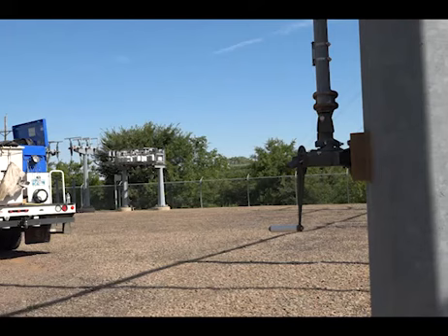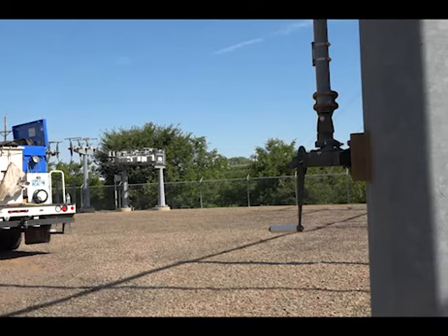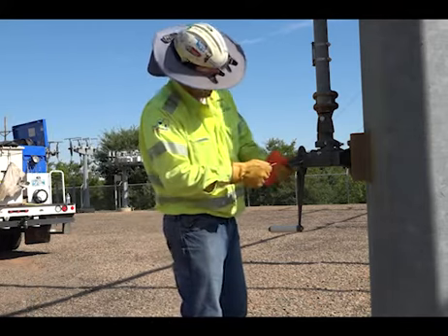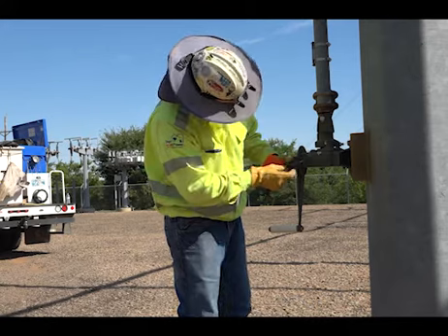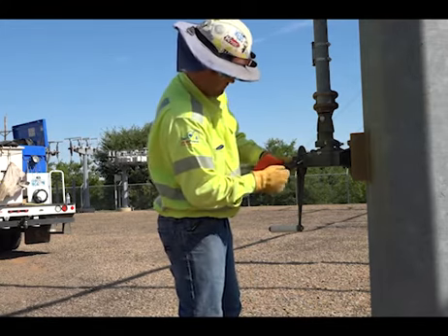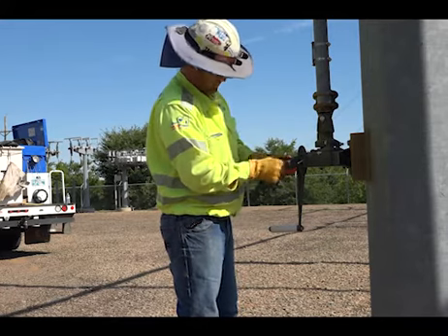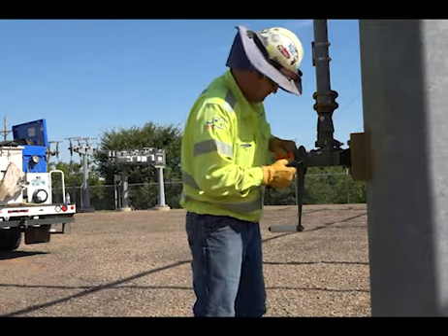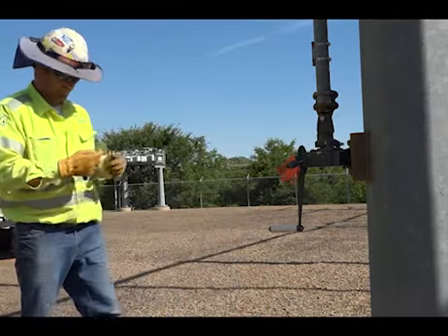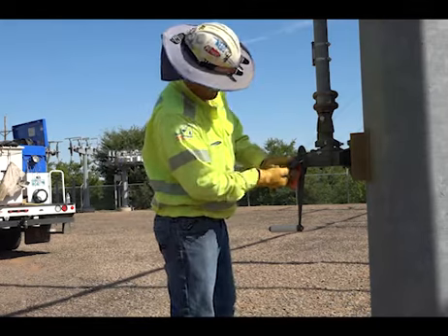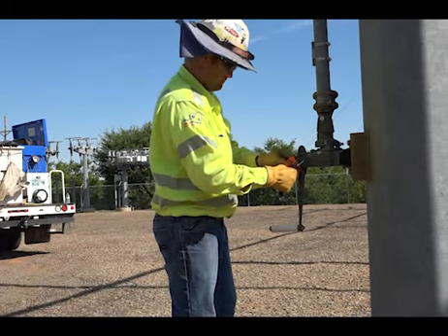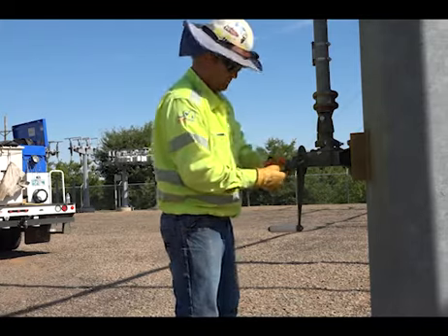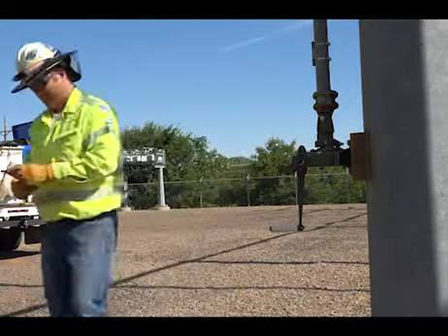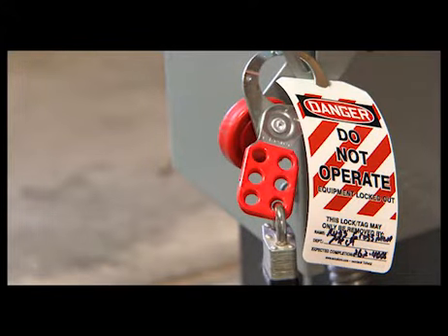Lockout, tagout. Every person performing work under a lockout, tagout clearance must be trained and understand the requirements of the lockout, tagout procedures. Be listed on or signed on to the clearance or switching procedure before performing any work. For substation and switchyard switching procedures, the person must use appropriate hold order cards on devices that are opened or closed as part of the switching procedure, along with the appropriate padlock on the device. Attempting to restart or re-energize equipment or systems that are locked out or tagged out is prohibited, and any violation will result in ejection from the site.